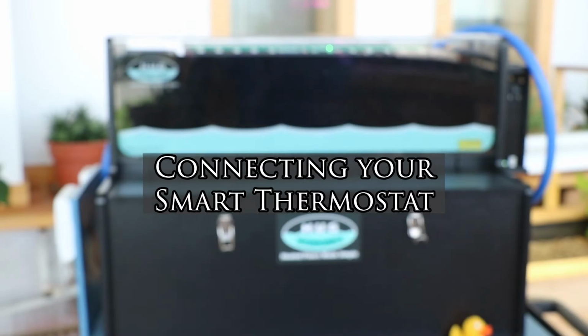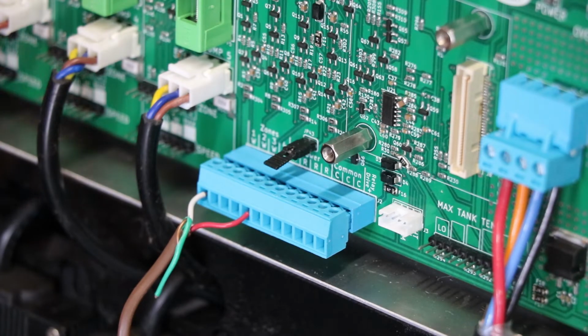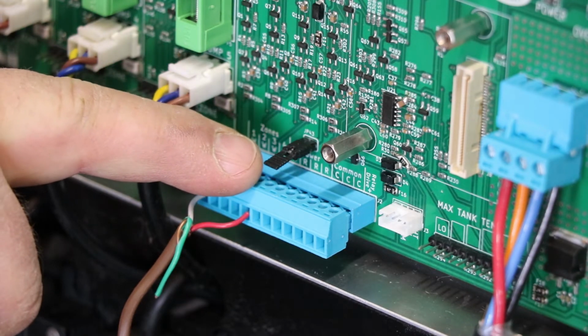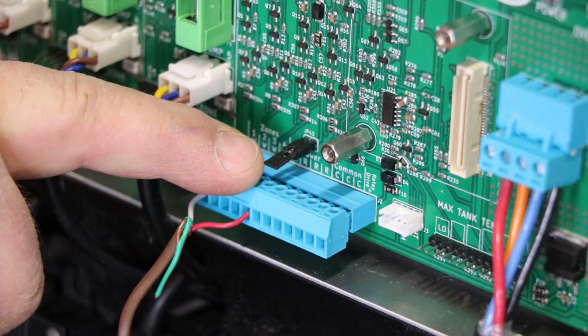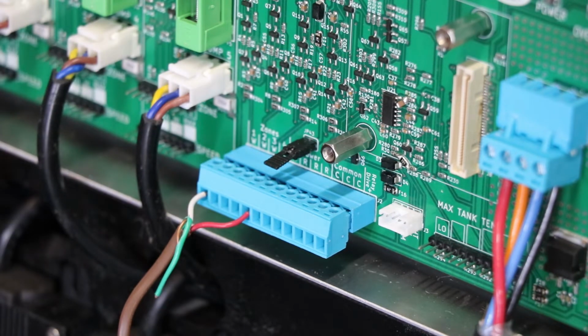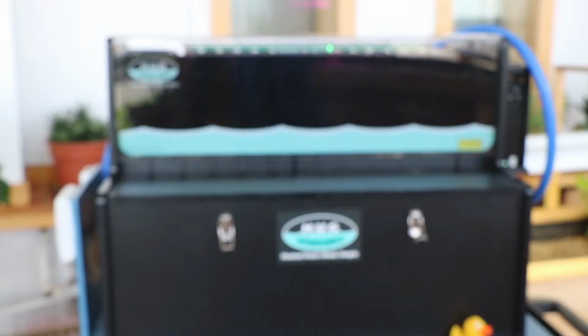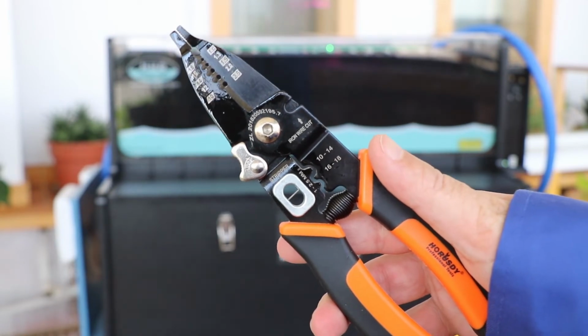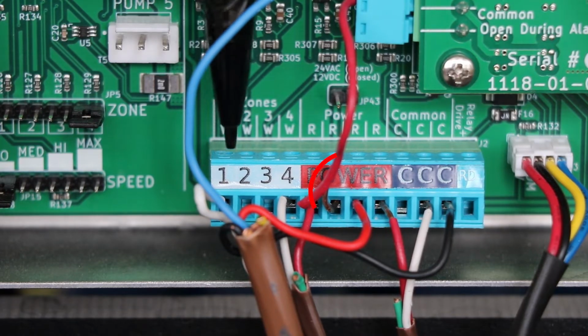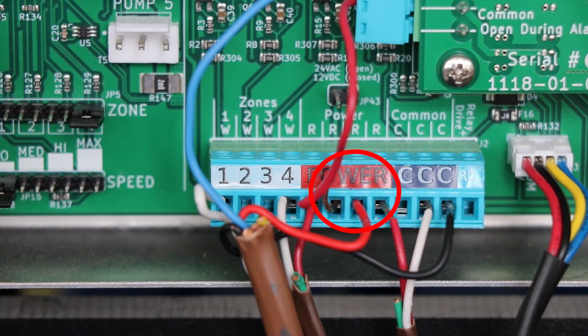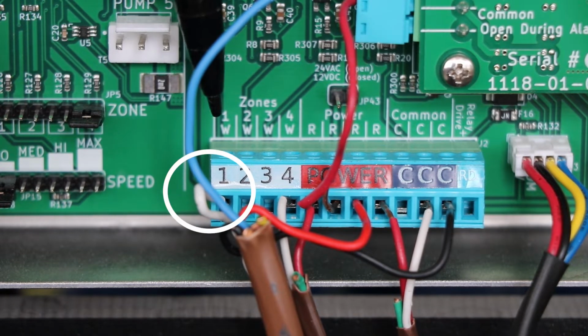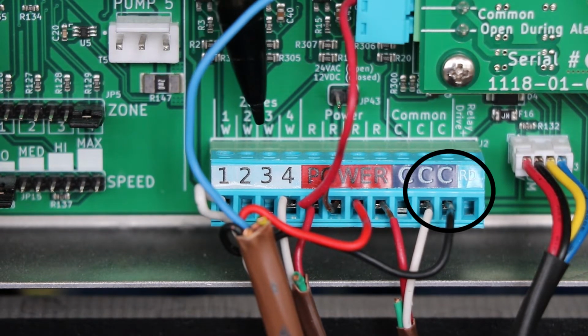If you're installing a smart thermostat, there's one more step you need to do. First, you'll need to remove jumper JP43, the one above the power section on the control board. Then, strip three wires from the thermostat wires. These are the red, white, and blue or black wire.